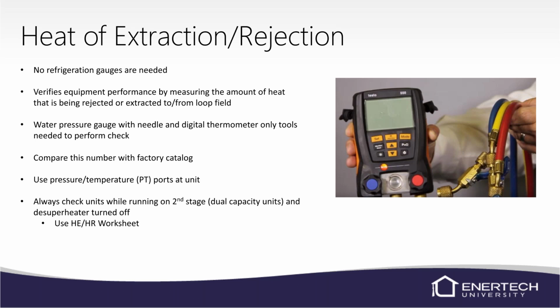Again, heat of extraction, heat of rejection. With heat of extraction or heat of rejection, basically there are no refrigerant gauges needed. You see a pair of refrigerant gauges here, and you don't need to use those to figure out the heat of extraction or rejection. The heat of extraction is the heat that you're pulling out of the loop field to put into the home, and heat of rejection is what you're putting back into the loop field from pulling from the home in your cooling season. The calculation is the same. It's just called something else when you're in cooling versus heating. Again, it verifies equipment performance that is either being rejected or extracted from or to the loop field.